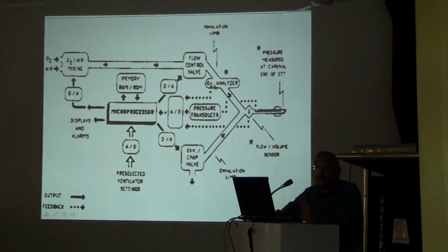So basically, remember only, you have to have an oxygen analyzer at the outlet to ensure that this 50% is displaying here as 50%, FiO2 0.5. Now you are sure that the machine is working properly. I have set 50%, and the air coming out toward the patient is 50%. Now you allow this air to go into the patient's lung by closing this valve.